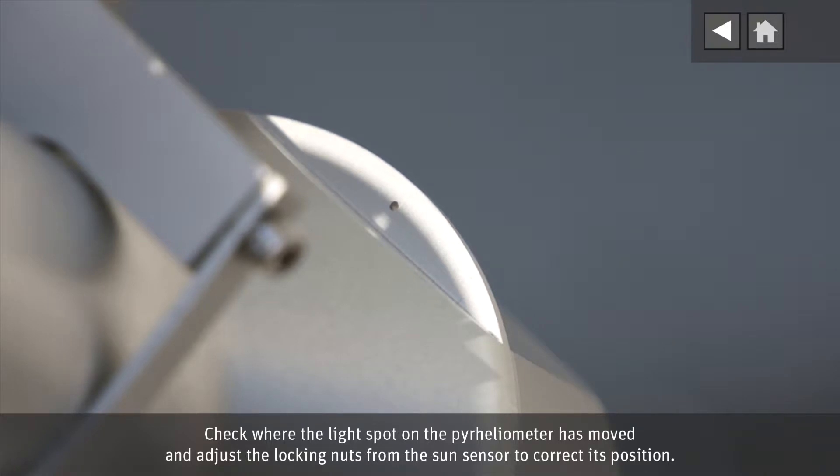Check where the light spot on the pyrheliometer has moved and adjust the locking nuts from the sun sensor to correct its position.